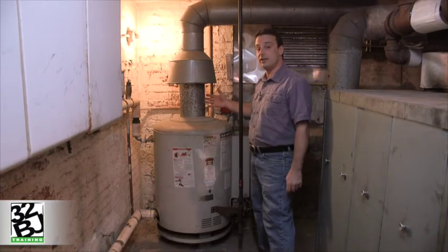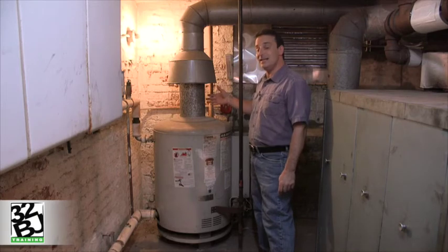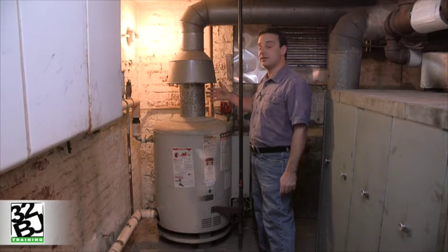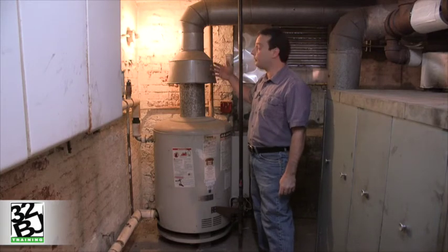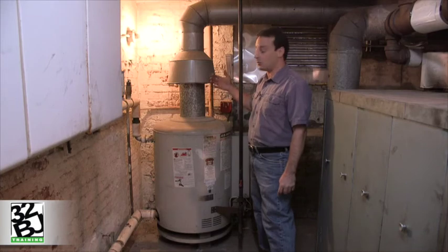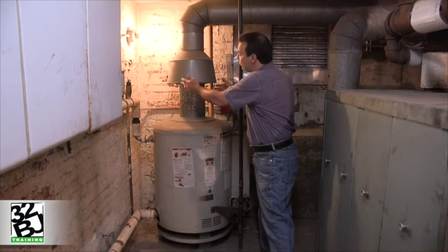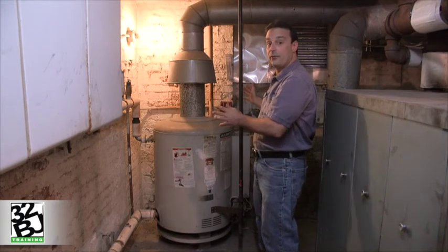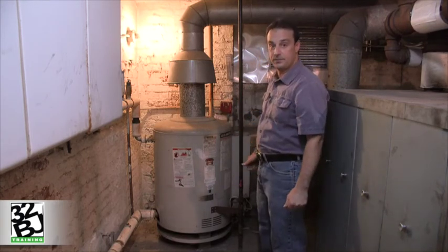One of the inefficiencies surrounding this hot water heater is the inability to control that natural draft. In some cases, poor draft or blockage in the breeching or the chimney can cause spillage, which will allow those gases of combustion to spill out of the bell damper, increasing the risk of carbon monoxide related issues.